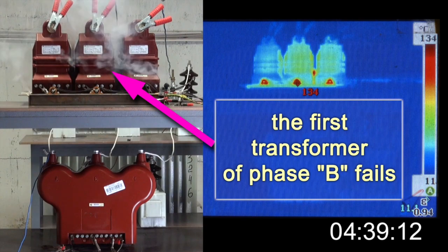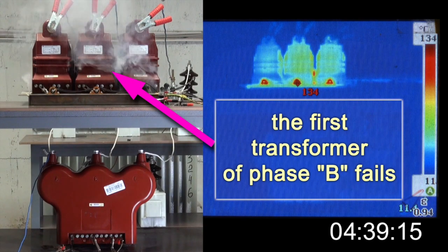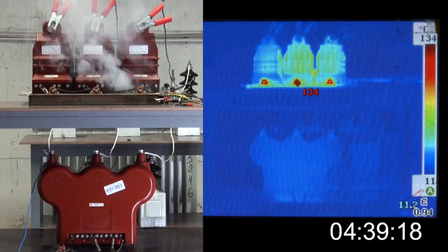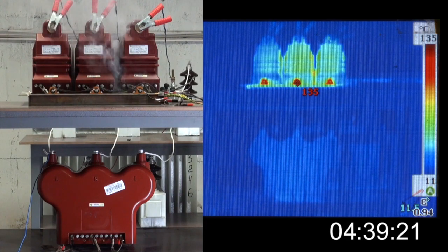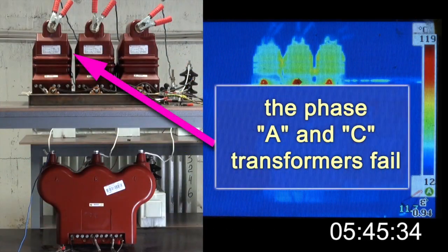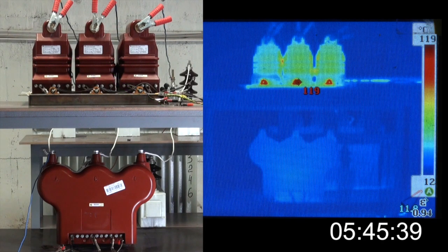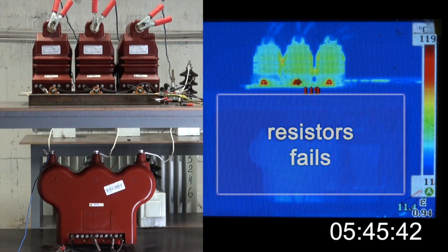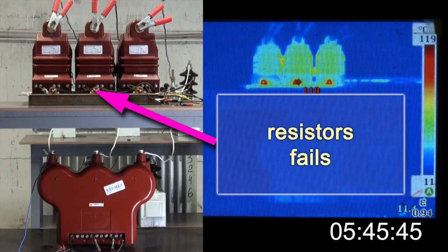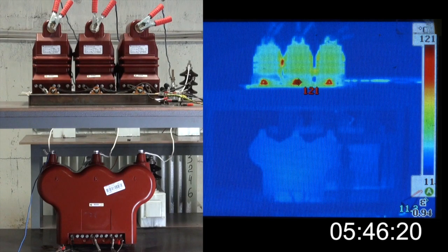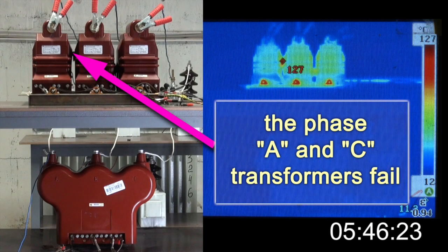Due to the high current inside the transformer, the windings overheat and an internal short circuit appears. The transformer begins to heat up quickly and thermal destruction of the transformer case occurs. At this point, the test could already be completed, since an accident had already occurred on one of the 3 single-phase transformers, but the test was continued for clarity. After a short time, the phase A and C transformers fail. In addition, explosions of resistors continue. In the picture from the thermal imager, you can clearly see the initial places of heating of the transformers and the cause of their damage.